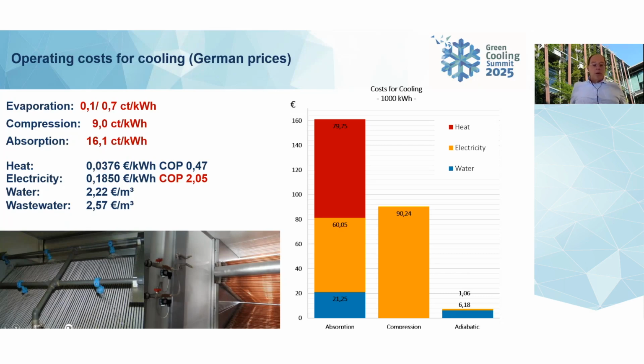For example, the compression system was promised that we have a coefficient of performance of 3.7, but we measured 2.05. And this is quite typical. So we are promised normally laboratory works, but if you compare that with the real performance during a year, it will drop until 2. So, yeah, and therefore, it's 160 times more expensive or 90 times more expensive if you compare this to evaporative cooling. The next slide, please.